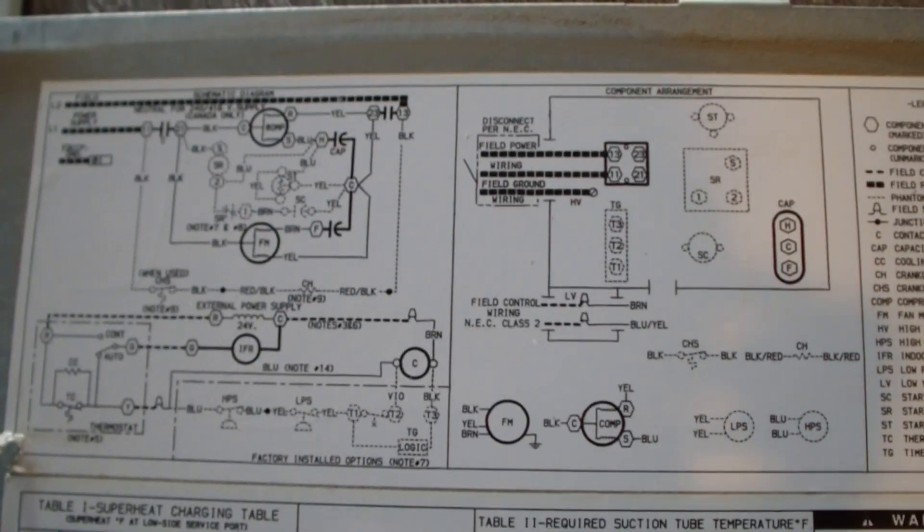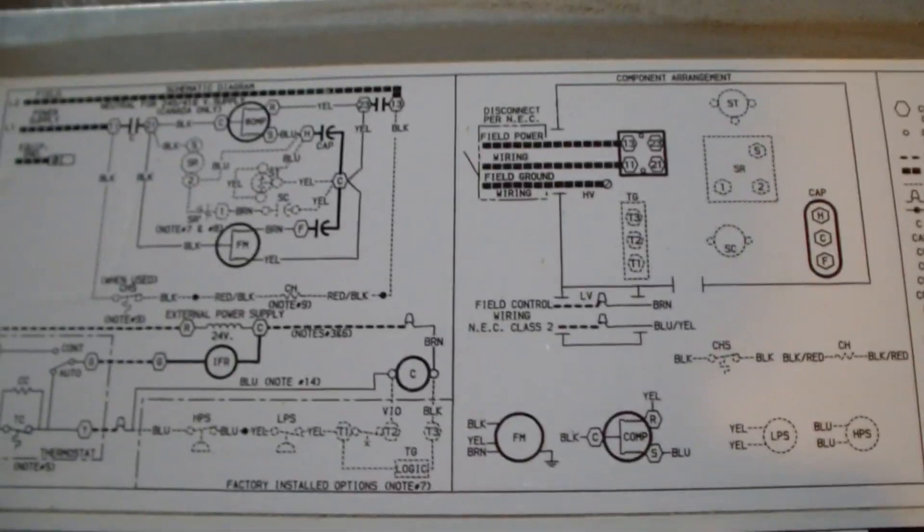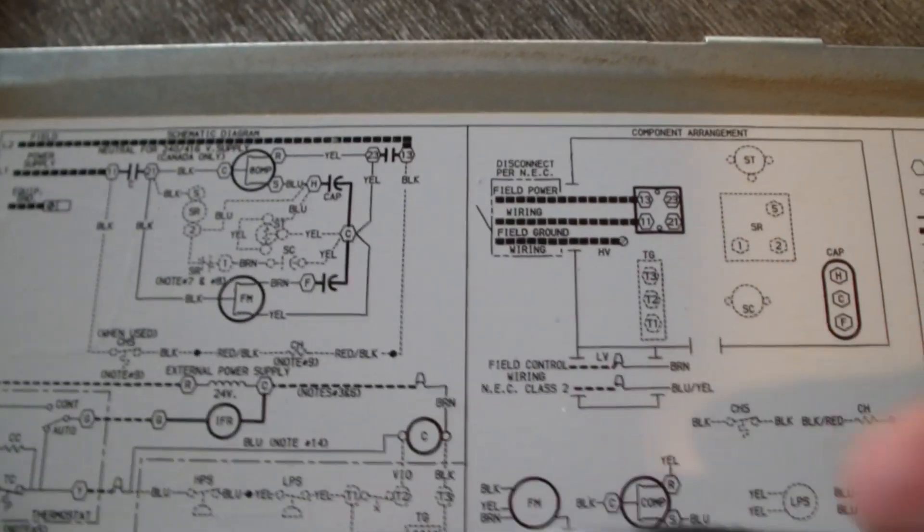Here's the schematic that was on the inside door. Let's take a look at this thing and see if we can figure out what's going on. Remember that big mess, that universal capacitor with all those things on there? Let's take a look. Here's the capacitor they show here - they show a dual capacitor.